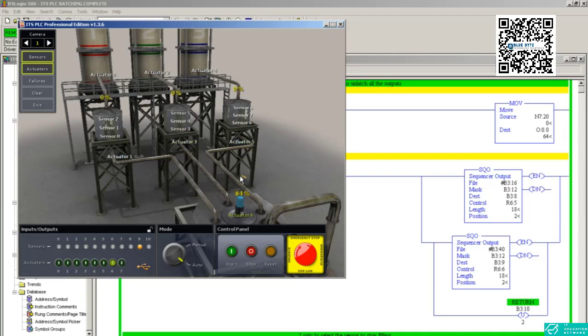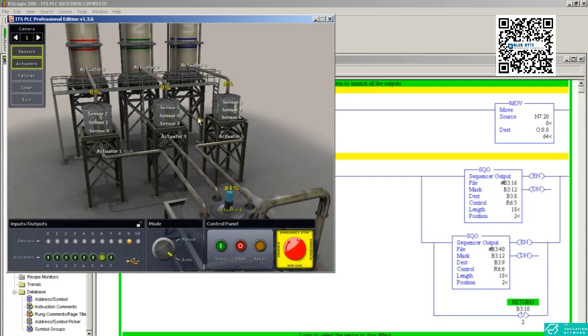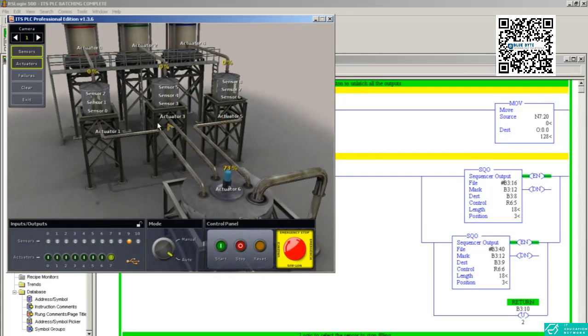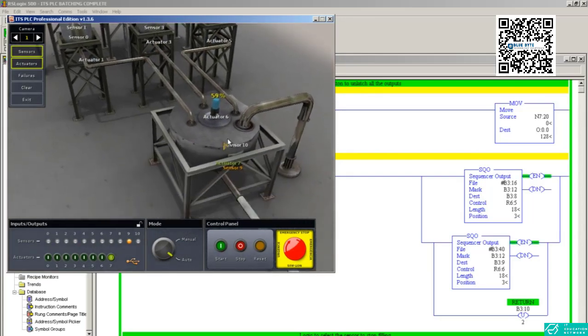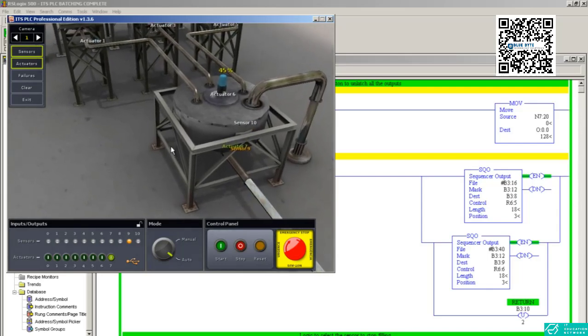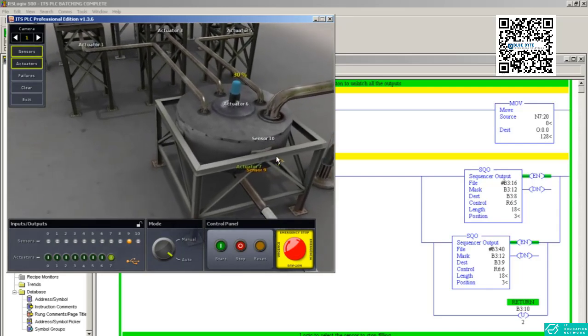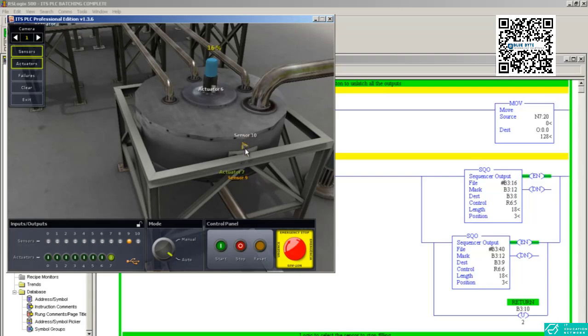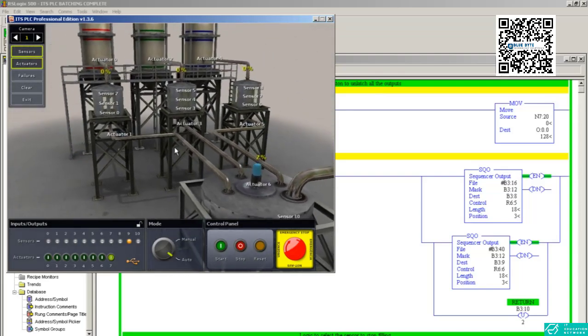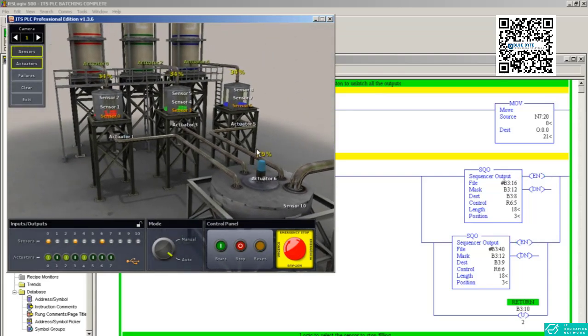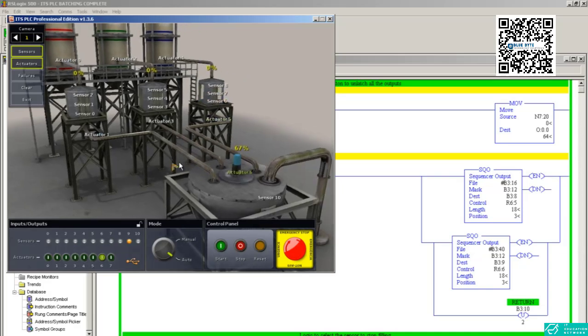Now to link that to our SCADA screen, we have to define the tags. You have all the sensors here from sensor 0 to sensor 10. These are two sensors, 9 and 10 - one for low level, one for high level. Then you have 8 actuators. So we have to make the tags in our HMI SCADA screen, and then link those tags with the PLC screen.